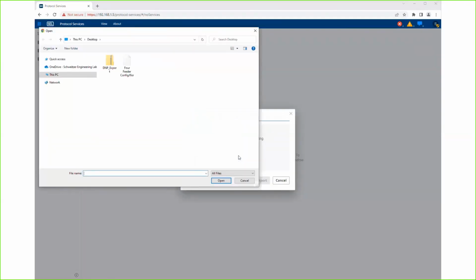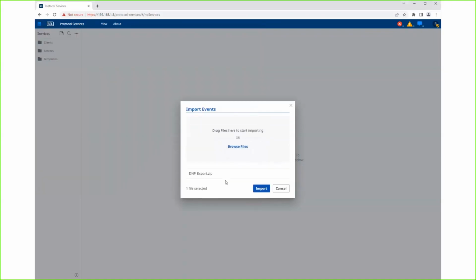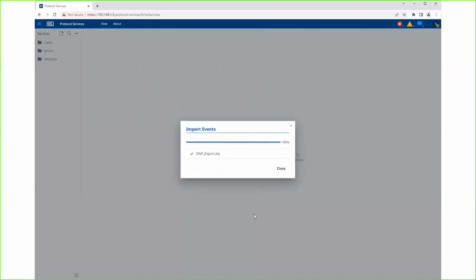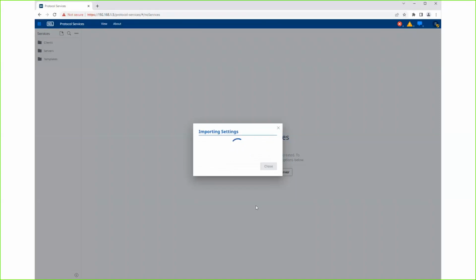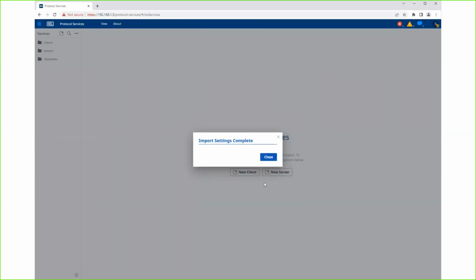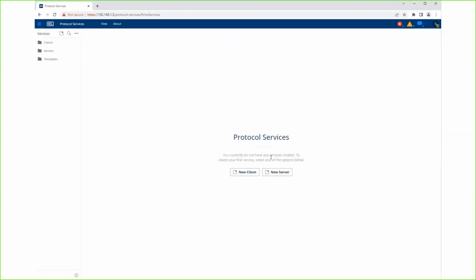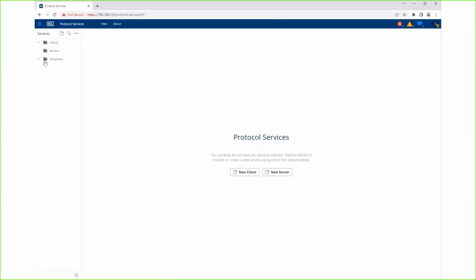What I want to demonstrate here is just like you can import and export your DMS Designer configuration, you can import and export DNP settings as well, and that's what we're doing here. So what I'm going to do is import DNP settings for all 4 feeders worth of breakers and reclosers. And give that just a second. So what's happening in the background here is a connection is being created and set up for every client that was in that import, and there were a bunch of them.